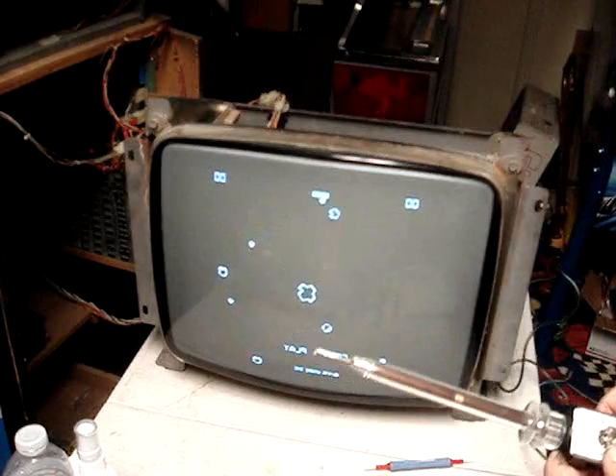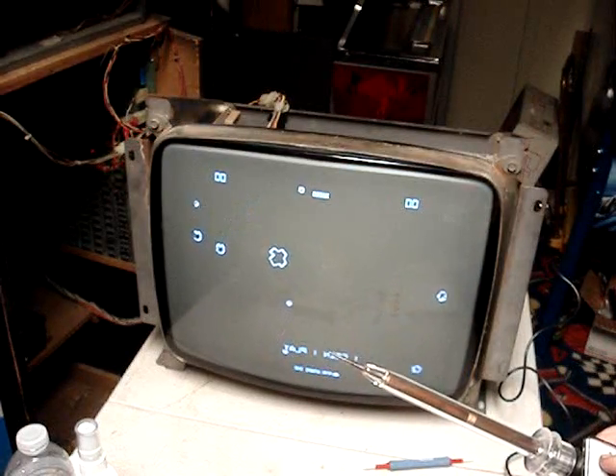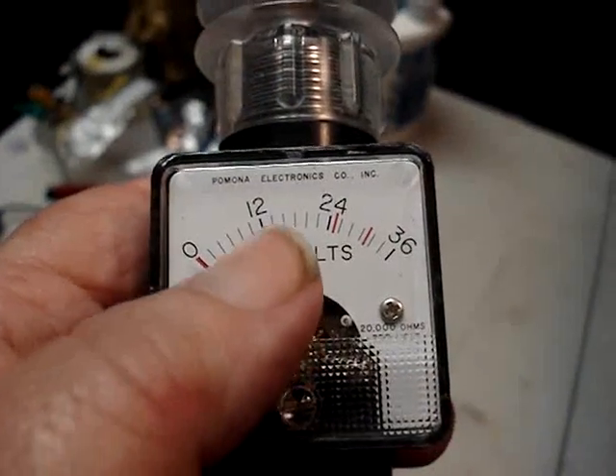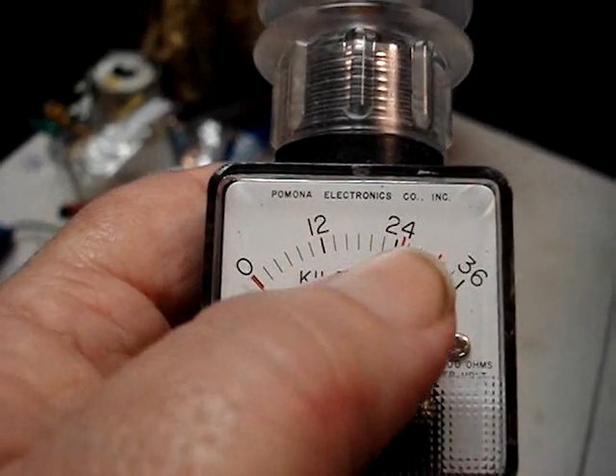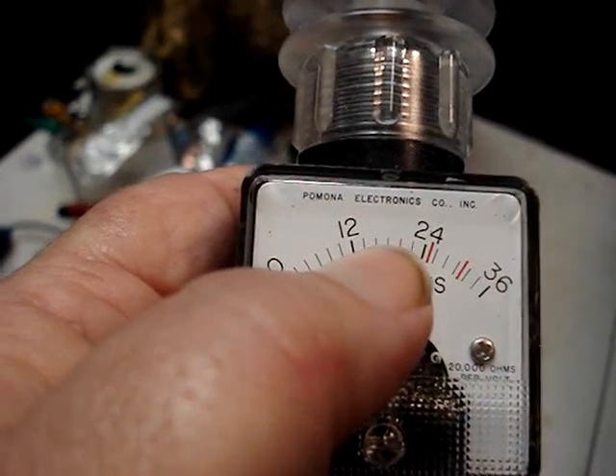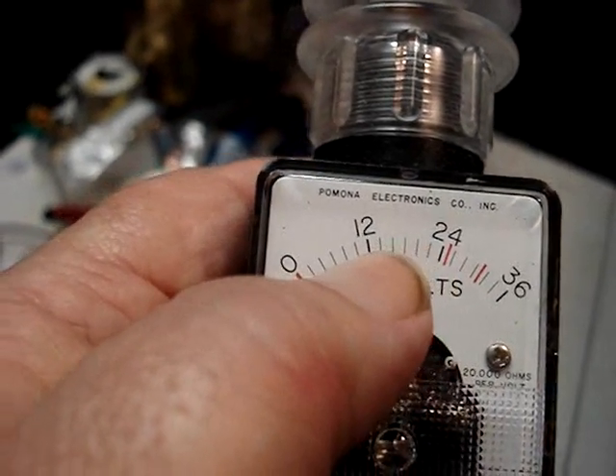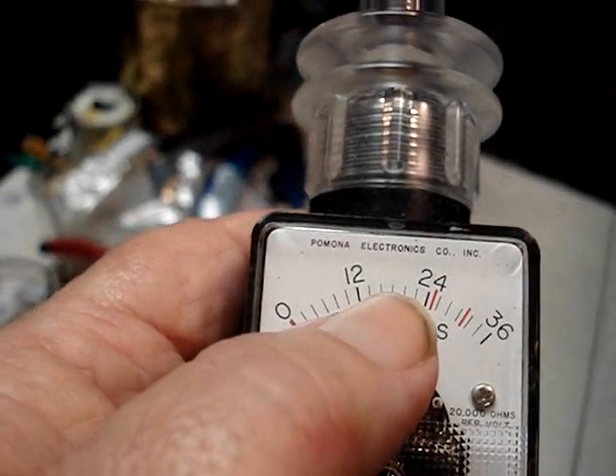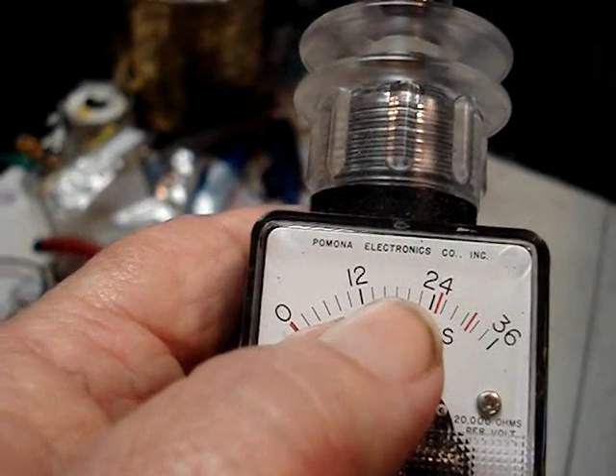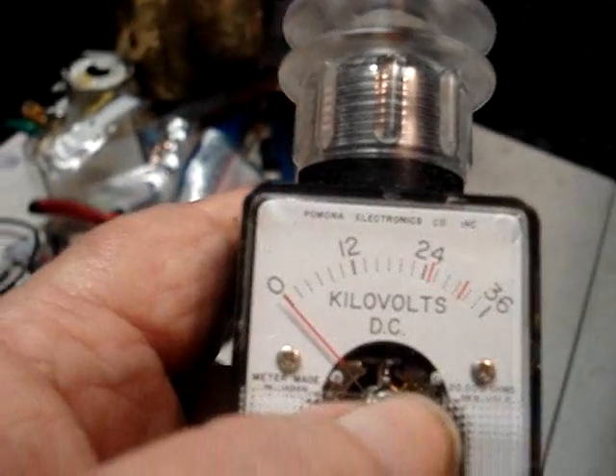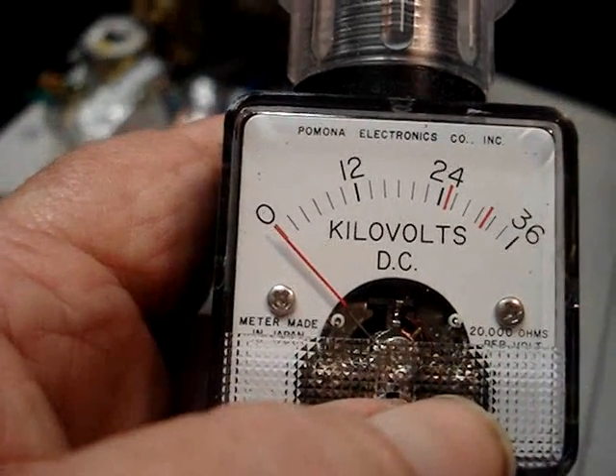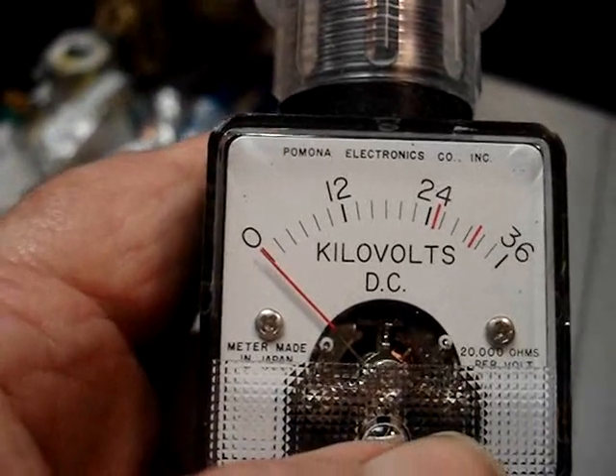Let's see what this is on this scale. 12, the next is 24. Okay, well, I was getting a high voltage reading. It was one mark over the 12, and the next is 24. So going by this scale right here, each mark is 2k volts. So that means I'm reading 14,000 volts. And I think it's supposed to be like 14.5. So with this scale right here, that seems to be right in the range where it's supposed to be. So I don't think I'm going to have a problem now with the high voltage.